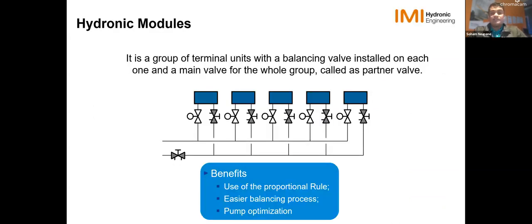So the way to do it basically is by creating hydronic modules. And when I say creating hydronic modules, we talked about the partner valve. So when we have a partner valve going into this main, like your distribution pipe, and you have several other balancing valves downstream, this whole thing starts working as one unit. And what it does is it helps us use the proportional rule, which I'll explain later. And that basically helps us make the balancing process much easier and work independently in modules and optimize the pump as well. So let's get started and see how we create modules, okay?